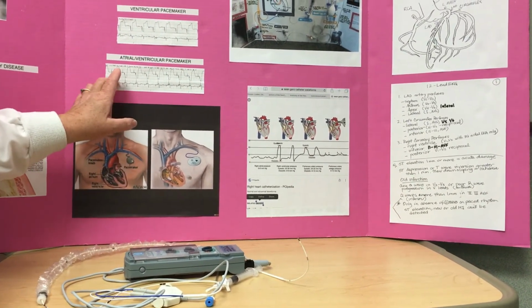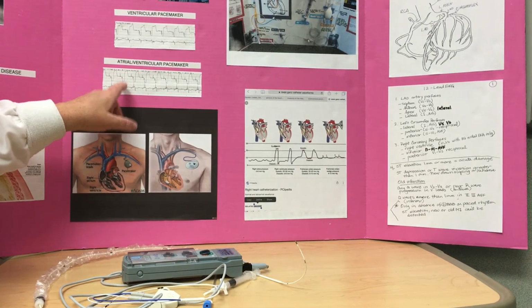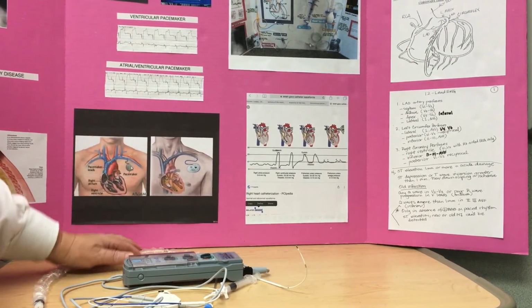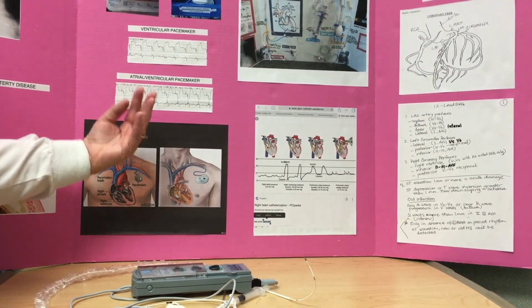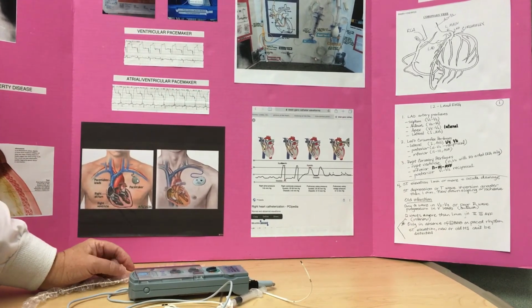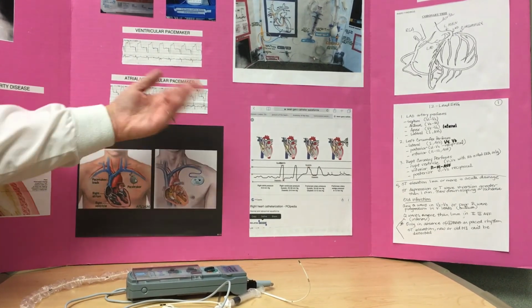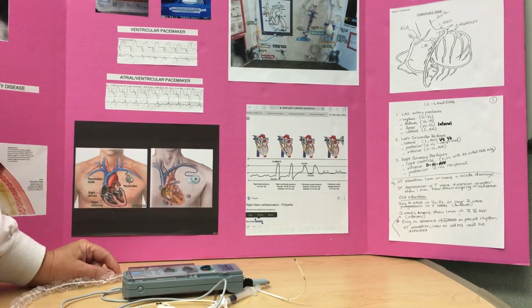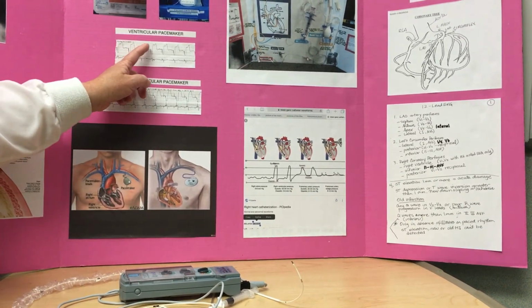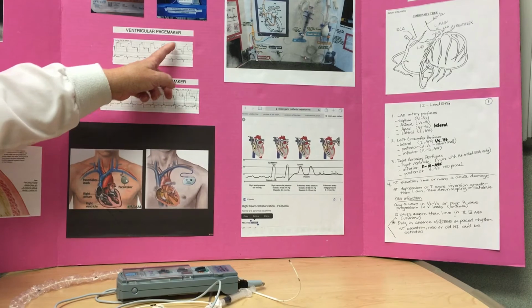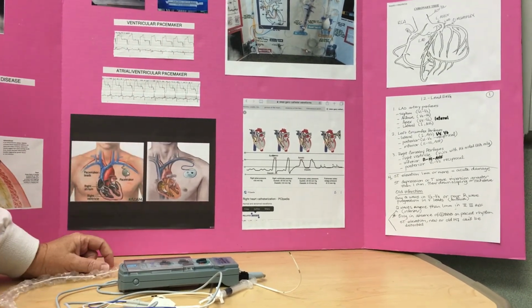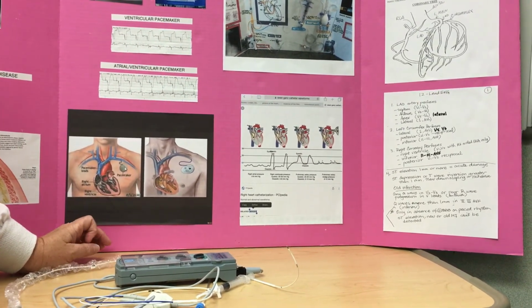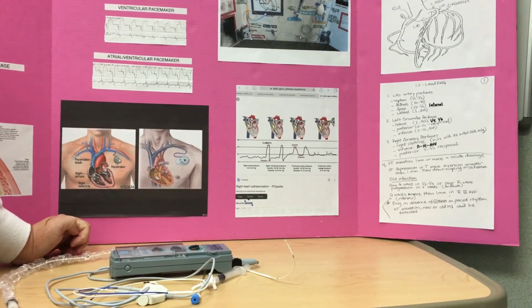Also, there's a problem if you're spiking on top of the patient's own beat. That means you're not sensing the patient's own pulse, and it's trying to pace over the patient's pulse. That would be spikes on top of the QRSs or in places they shouldn't be. That would be a loss of sensitivity, and that would be another thing you would need to let the doctor know.